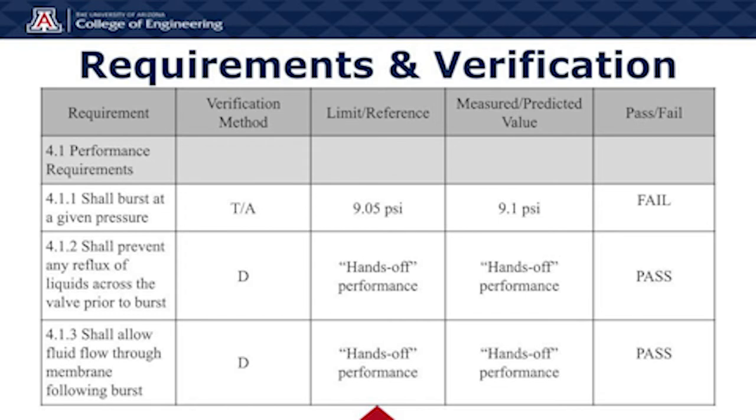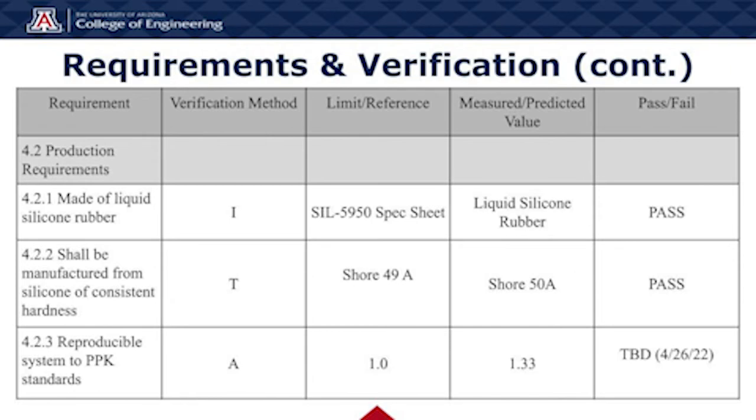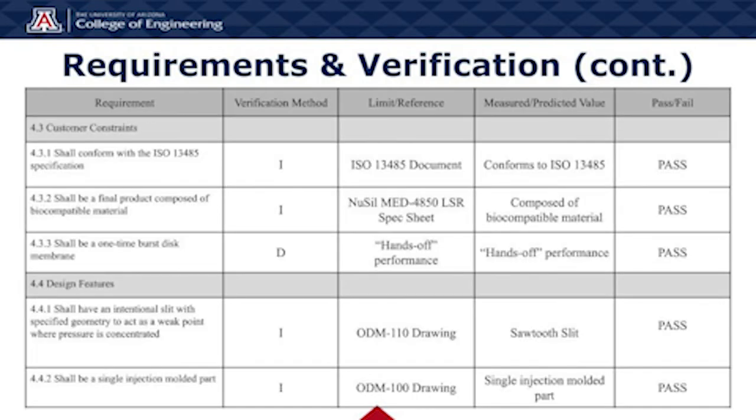The performance requirements for this project are as follows. 4.1.1 shall burst at a given pressure. 4.1.2 shall prevent any reflux of liquids across the valve prior to burst. 4.1.3 shall allow fluid flow through the membrane following the burst. The production requirements are: 4.2.1 made of liquid silicone rubber; 4.2.2 shall be manufactured from silicone of consistent hardness; 4.2.3 reproducible system to PPK standards. Customer constraints are: 4.3.1 shall conform with the ISO 13485 specification; 4.3.2 shall be a final product composed of biocompatible material; 4.3.3 shall be a one-time burst disk membrane. Section 4.4 design features: 4.4.1 shall have an intentional slit with specified geometry to act as a weak point where pressure is concentrated; 4.4.2 shall be a single injection molded part.